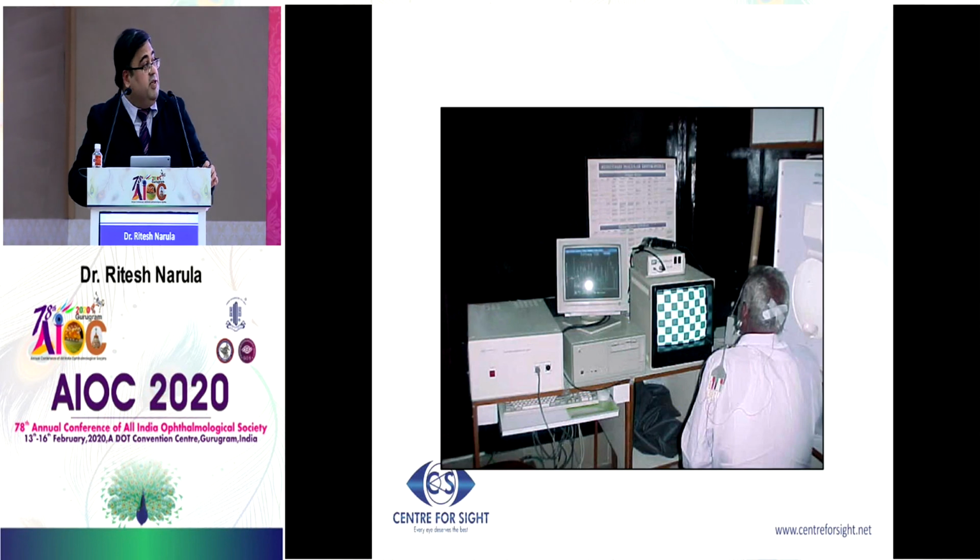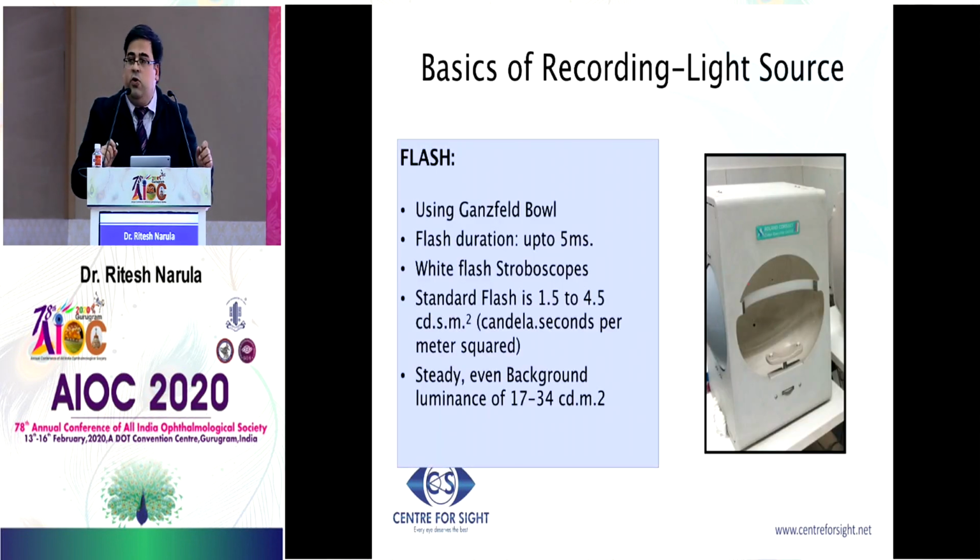And this is how a patient is prepared for a VEP. I'm showing it here just to finish it here, where the occipital area is cleaned with an abrasive alcohol swab, and then the electrodes are attached. To record, unlike ECG where the heart beats on its own, to generate signals within the eye you need a stimulus. For stimulation you need a light source.